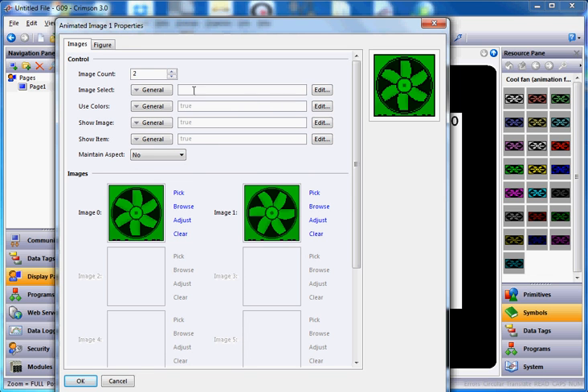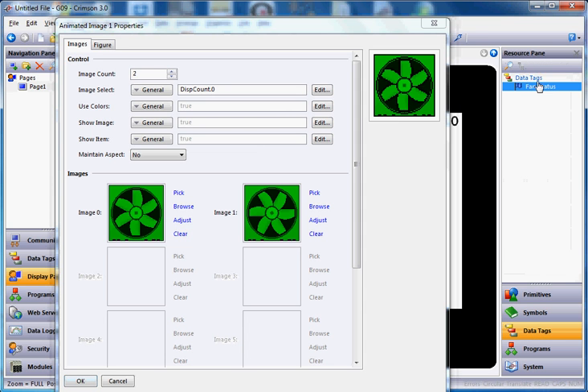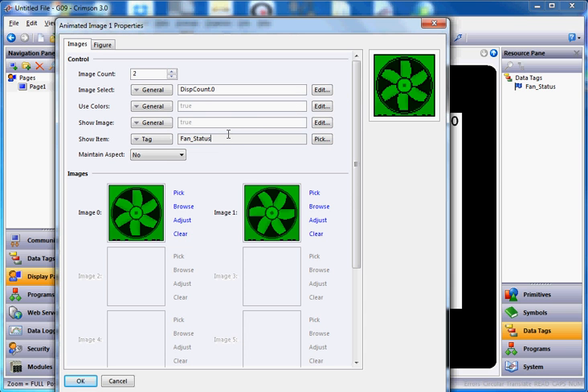Up here where it says image select, we're going to use a pre-built function called disp_count. So I'll type disp_count — D-I-S-P-C-O-U-N-T — then a period dot zero and Enter. Disp_count is a tag that simply counts the number of times the page has been refreshed. By doing dot zero I'm looking at just bit zero of that integer, which gives me a flip-flop between one and zero — perfect. Down here where it says show item, I only want this whole thing to show up whenever the fan is on. So I'll go to data tags on the right and drag my fan_status tag into the show item field. I'll click OK.